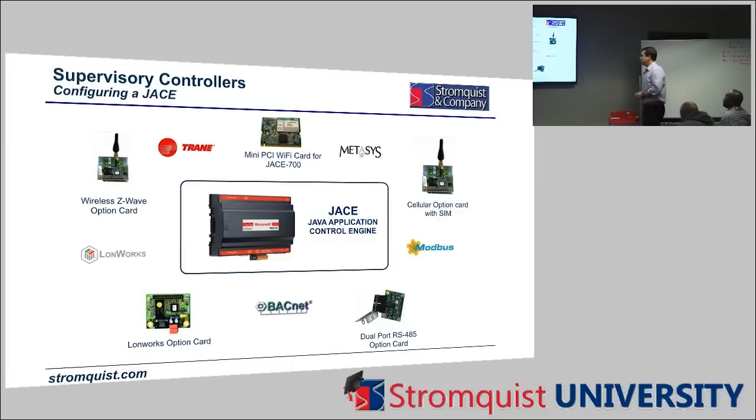Now, it doesn't stop right there. You have to get the driver as well. So that RS-485 card, like I said, talks to several different communication protocols. And when I install it, it doesn't do anything until I install the driver, which says, hey, this card is going to be used for BACnet. If I wanted to use this card for Metasys, the Johnson Controls N2, then I'd put that driver in.